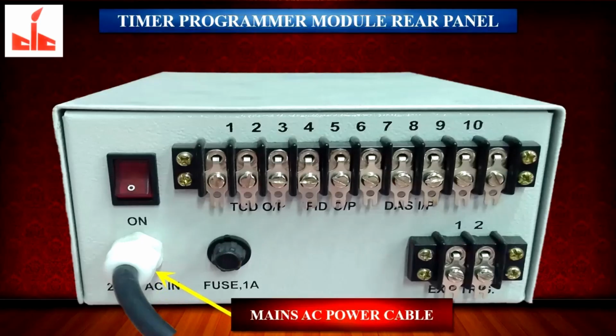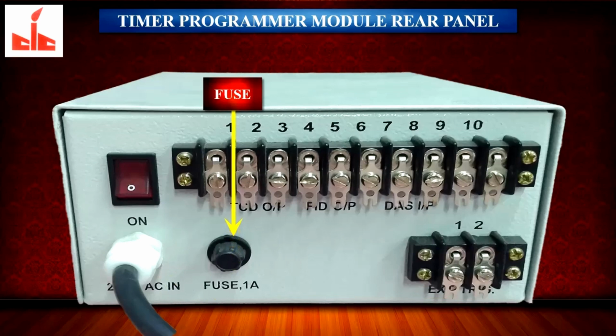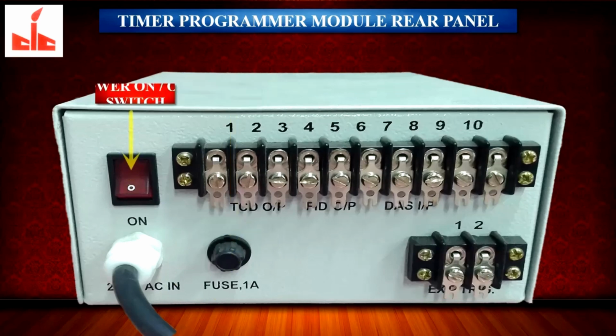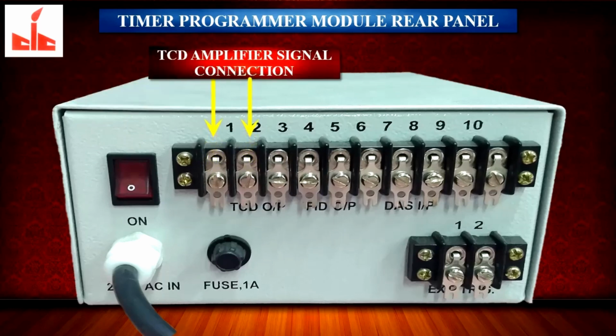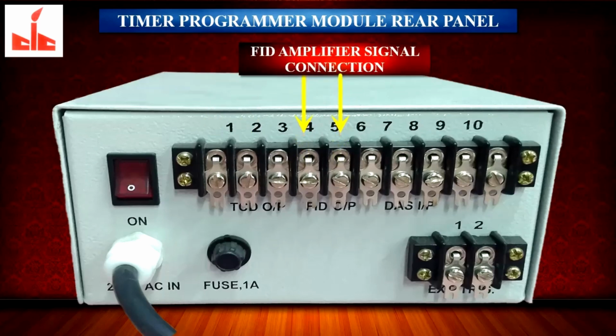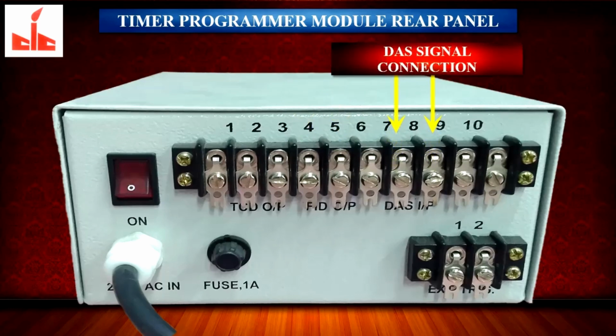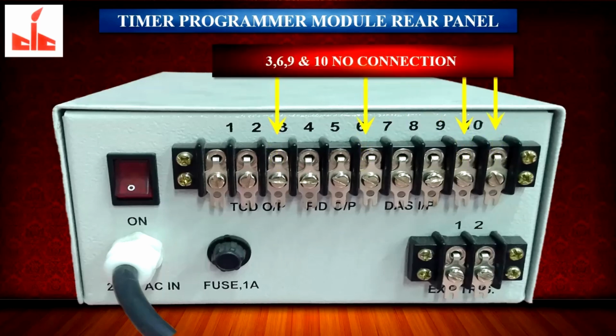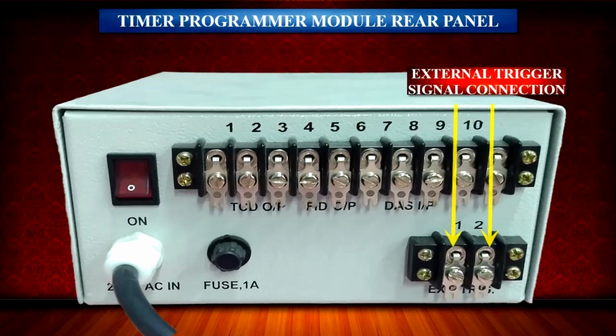This is mains input, AC power supply cable. This is fuse. This is power on and off switch. This is TCD amplifier signal connection terminal strip. This is FID amplifier signal connection terminal strip. This is data acquisition signal connection terminal strip. Terminal number 3, 6, 9, and 10 are not connected with any cable. This is external trigger, signal connection terminal strip.